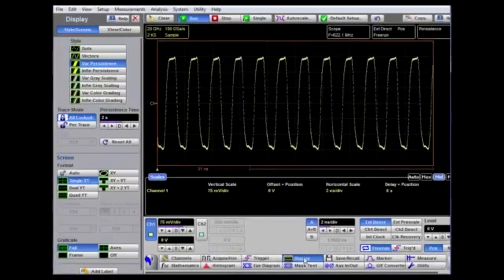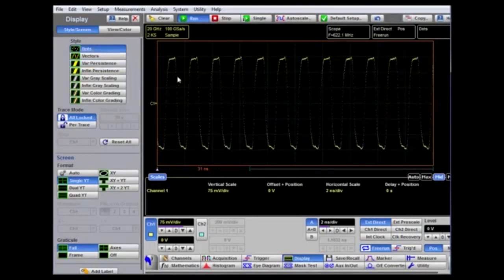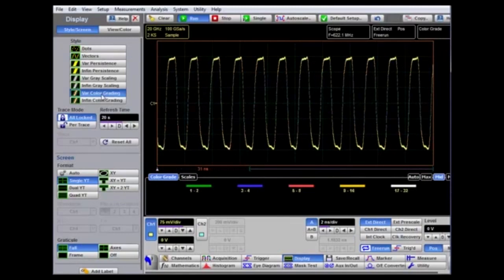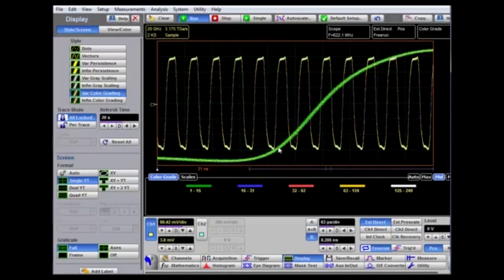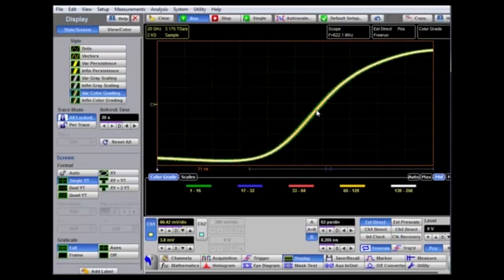In the display menu, many more waveform display formats are available. The default is variable persistence, but also available is dots mode where we can see the raw sample points, which can be joined using vector mode. There is also a color grading display that gives more information about the waveform acquisition. Zooming in on the rising edge, we can see where sample points have been taken. Green indicates a few hits, white indicates many hits, and yellow shows the most frequent sample location — typically the center of the waveform, with occasional extreme values on the edges shown in green.